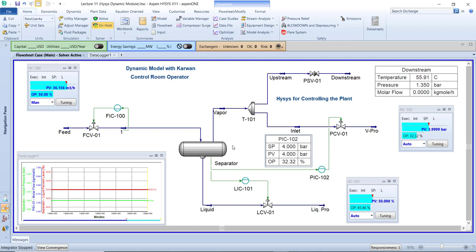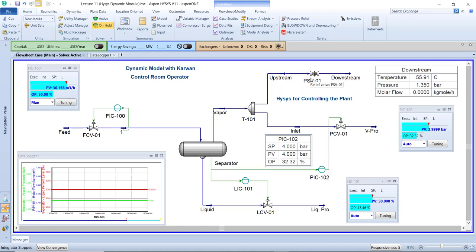The alarm system works like this: the separator pressure is set at four bar, but if the pressure reaches 4.8 bar, an alarm appears telling you 'please be careful, the separator pressure has increased — you must take action.' Why? Because if you don't take action, your process becomes dangerous. If you don't act as a control operator, the next step is the PSV opens. When the PSV opens, it makes a very loud, strange sound that you can hear clearly in the field.